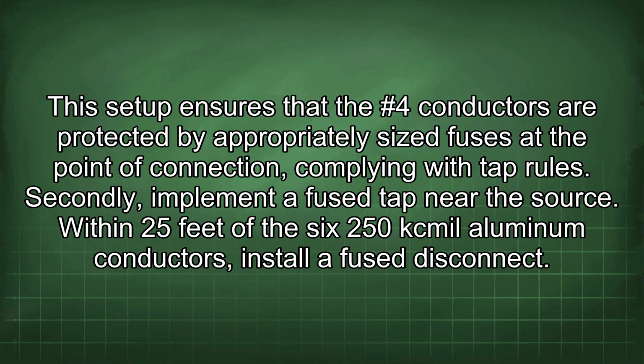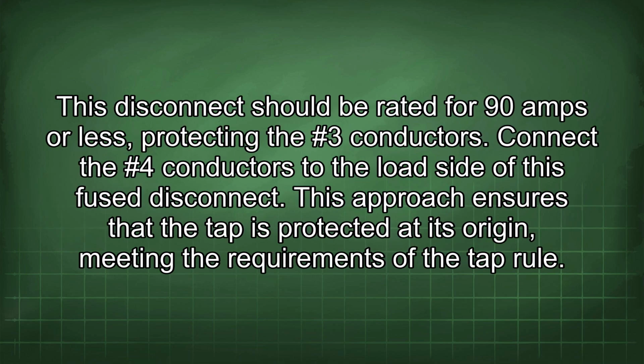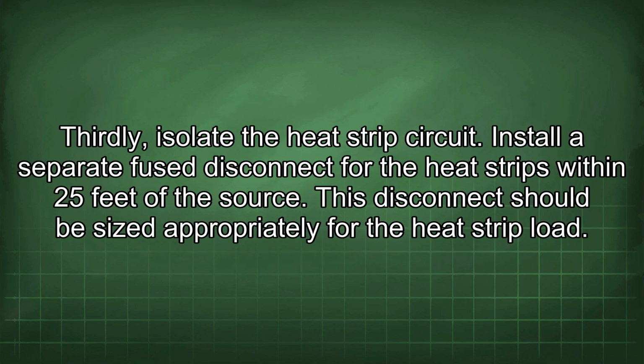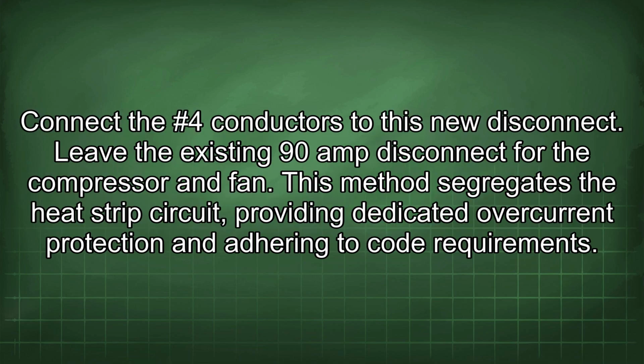Within 25 feet of the 6 250 kcmil aluminum conductors, install a fused disconnect. This disconnect should be rated for 90 amps or less, protecting the #3 conductors. Connect the #4 conductors to the load side of this fused disconnect. This approach ensures that the tap is protected at its origin, meeting the requirements of the tap rule. Thirdly, isolate the heat strip circuit. Install a separate fused disconnect for the heat strips within 25 feet of the source. This disconnect should be sized appropriately for the heat strip load. Connect the #4 conductors to this new disconnect. Leave the existing 90-amp disconnect for the compressor and fan. This method segregates the heat strip circuit, providing dedicated overcurrent protection and adhering to code requirements.